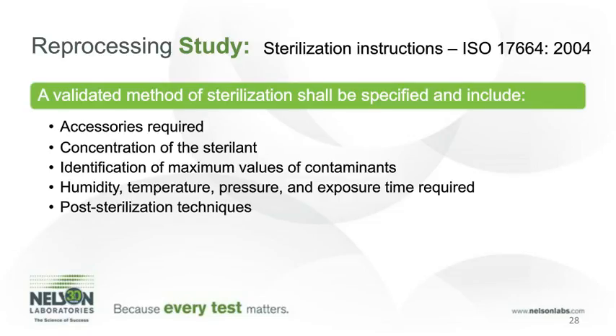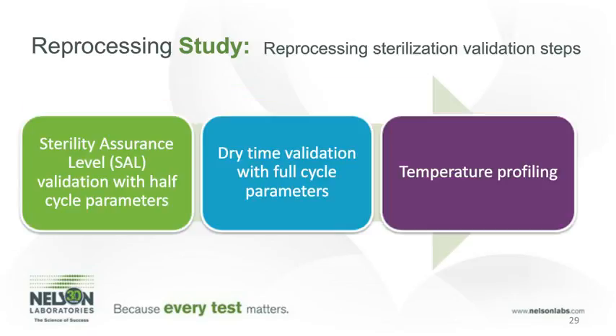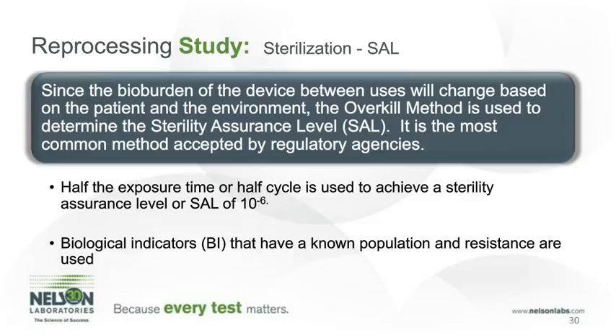To perform a sterilization validation, we first perform a sterility assurance level validation with half-cycle parameters. Next is the dry time validation with full-cycle parameters, and then temperature profiling of the entire case to ensure that every part of the case is getting up to the correct exposure time and temperature. The overkill method is utilized for the sterility assurance level validation since the bioburden of the device will change based on different patient use and also the environment of each healthcare facility. Due to this, we are testing for the half-cycle time to kill a sterility assurance level of 10 to the minus 6. In this testing, biological indicators are utilized that have a known population and resistance.